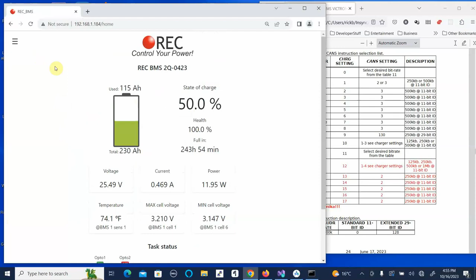Now the last part we're going to come back to is tasks. And here you have 2 configurable outputs that you can use for inverters, for a low temperature alarm, for a low temperature heater, a high temperature alarm. You've got a lot of options here. So if we select output number 1, each one of these outputs is meant to drive an interlock type of system. If you want to run a contactor or a heavy load off of it, you'll want to add a small interposing relay.